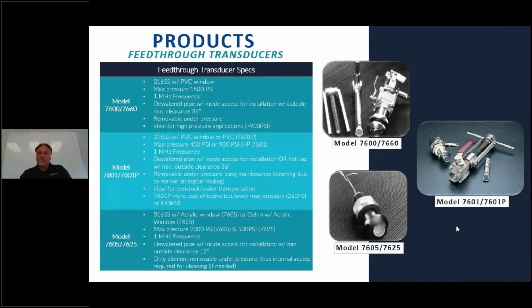On the product side, we have two main transducer types that we utilize. On this screen, we are showing our feed-through style transducers. So these transducers penetrate through the pipe wall, and we have basically three main models that are used for the hydro industry. The 7600 and the 7660 are a transducer and feed-through set with an integrated ball valve, so the pipe can be isolated when transducers are removed under pressure. Those are good to about 1500 psi, so that would be our high head application transducers.